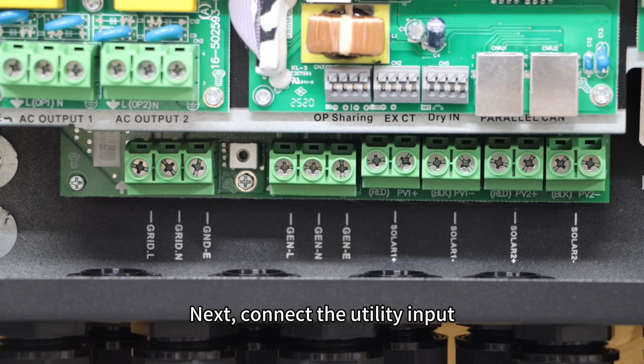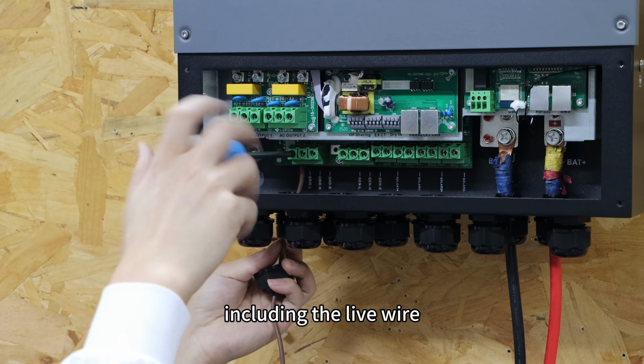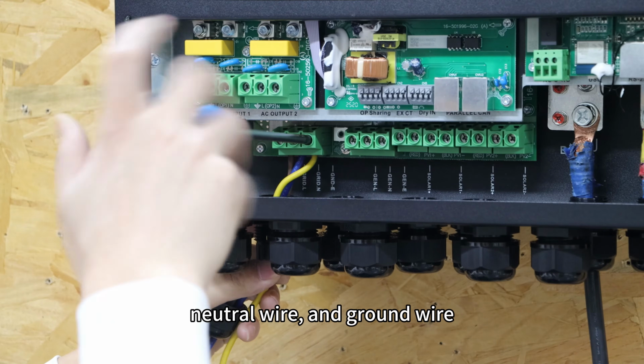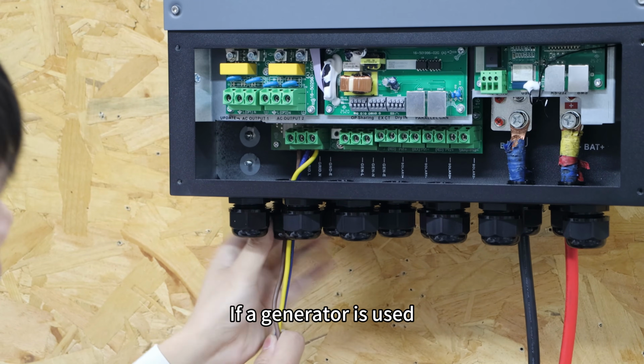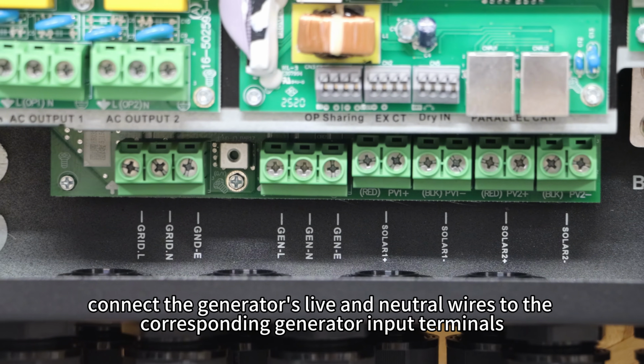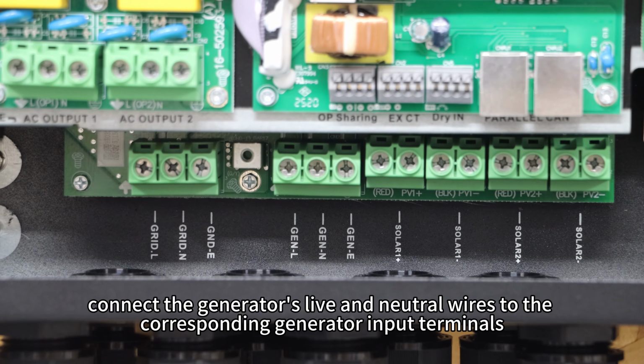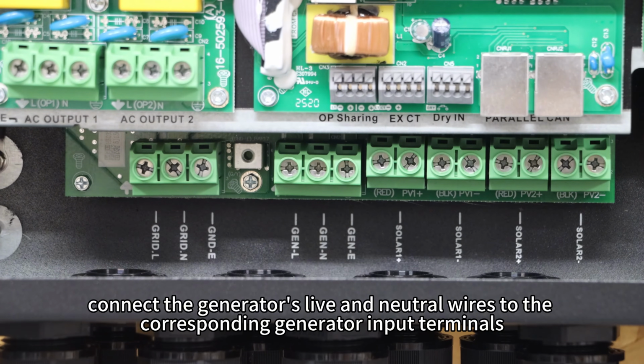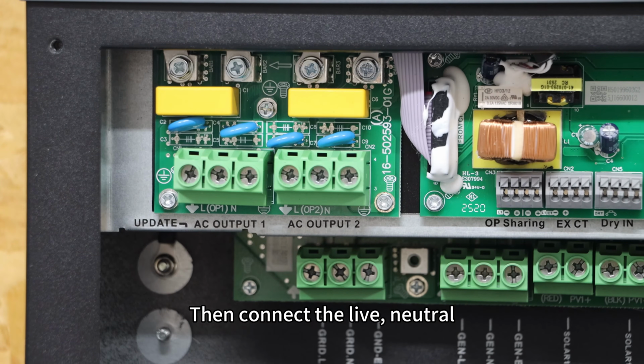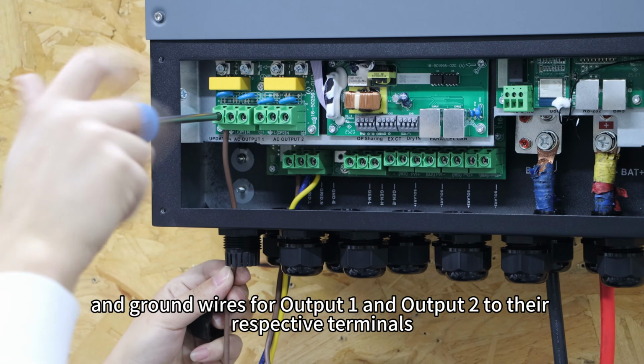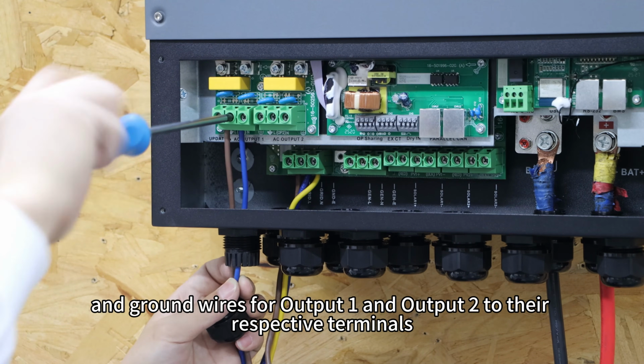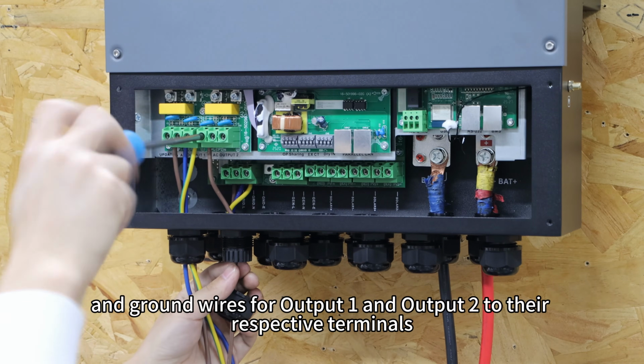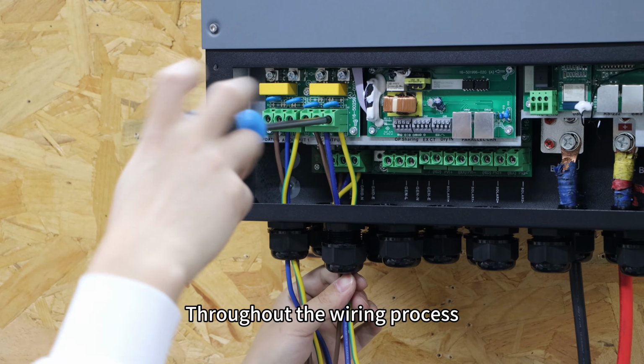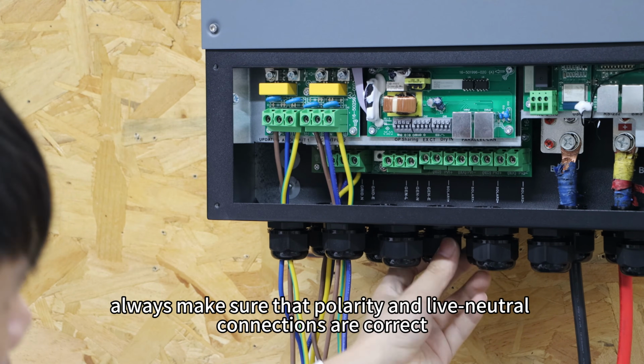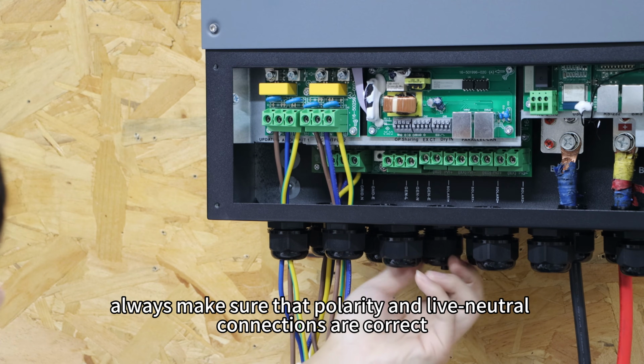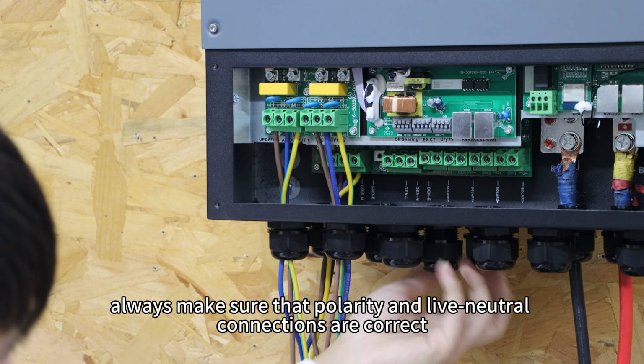Next, connect the utility input, including the live wire, neutral wire, and ground wire. If a generator is used, connect the generator's live and neutral wires to the corresponding generator input terminals. Then connect the live, neutral, and ground wires for output 1 and output 2 to their respective terminals. Throughout the wiring process, always make sure that polarity and live-neutral connection are correct.